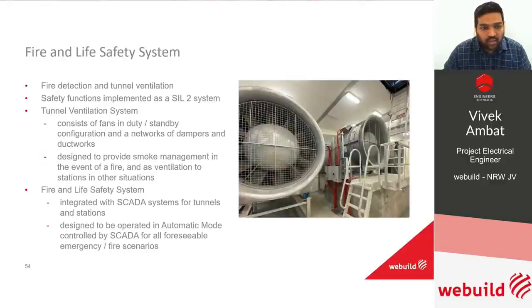All of these tunnel ventilation modes are controlled from our SCADA system, so it's fully automated, with also the option of allowing it to be operated manually if the operator in the control center wishes to do so. The SCADA system has also been designed to SIL2 and is currently going through a rigorous amount of testing and commissioning to satisfy the requirements of a SIL2 system.